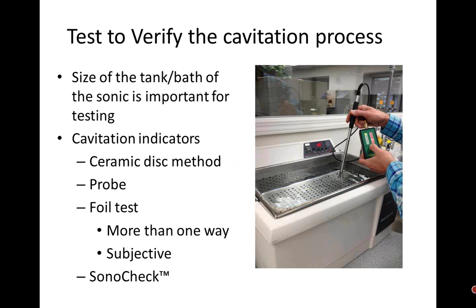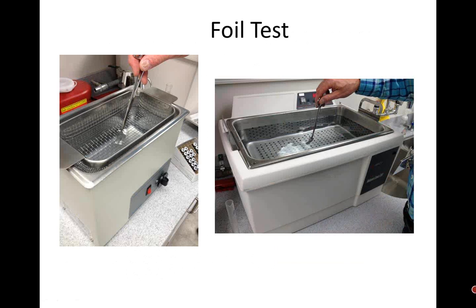There is a foil test, and that is also subjective. We're going to talk about it. And there is a Sonocheck, which was made specifically for cavitation. Again, we're talking cavitation. We'll talk about cleaning in a second. As you can see to the right there, there's the probe. It's very expensive. Not many people have it. But what also with the probe, you have to take the lid off to check it. So it's not very practical. I do have one when I go in, but you have to find a way in the automated, how do you get the lid up and go from there.